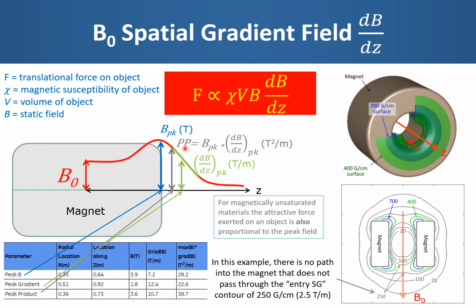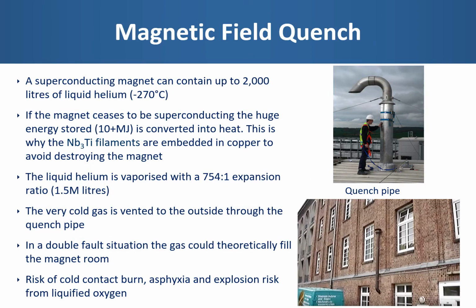Therefore, it is this spatial gradient that dictates the safety of certain MRI conditional devices or patients with implants with conditional requirements going into the magnet. I have already mentioned the possibility of a magnetic field quench. This can happen when the magnet suddenly ceases to be superconducting and the stored energy is converted to heat and the liquid helium is vaporized with a 754:1 expansion ratio. When this happens, the pressure inside the magnet rises and the burst disk ruptures and the helium vapor is vented to the outside through the quench pipe.